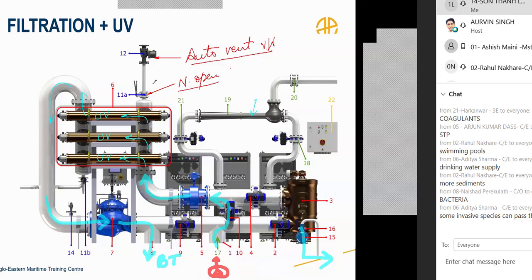Never close this valve 11A, because this has happened in one of the cases on a yard delivery ship, where somebody forgot to open this valve. Actually it should always be open. How it went closed, nobody knows, but it remained closed and the auto vent valve was useless from then onward, and air could not be taken out of the system. Because air is a bad conductor of heat, the UV lamps had air pockets in them and became overheated and started to burst. One after another, UV lamps were bursting. People could not figure out why it was happening. Then they came to know that valve 11A was closed. So it should actually be locked open.